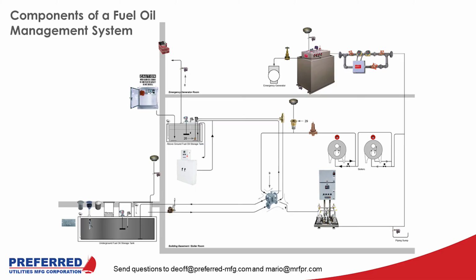When we look at a typical fuel oil handling system, we would see main tank, storage tank. We'll have the fuel pump set, the heart of the system. We'll see day tanks adjacent to the end users, fuel oil polisher or filtration systems, as well as multiple auxiliary components like sensors and valves that are recommended or required for the optimal operation of the system.